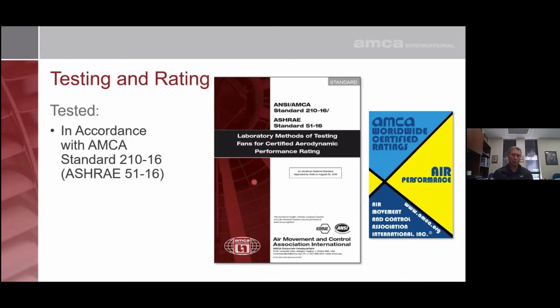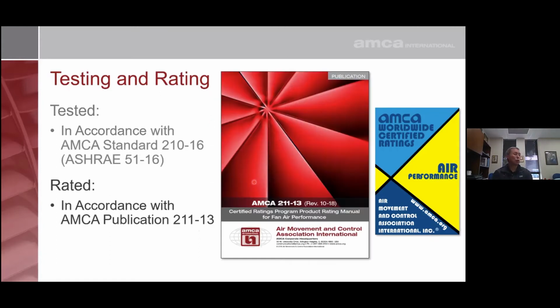And again, just like I was talking a little bit earlier, that methodology is applied from fan manufacturer X to fan manufacturer Y. Fans are rated in accordance with AMCA standard 211. And this gives us an acceptance tolerance or criteria for that fan test.